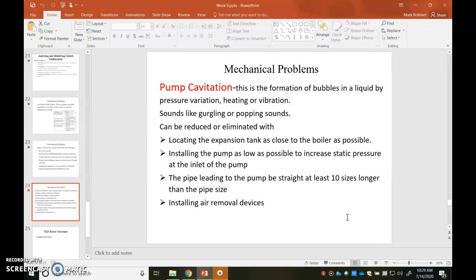boiler and the pump. The pipe leading to the pump must be straight, or at least 10 sizes longer than the pump size. So you can't have an elbow and then the pump. If the pipe is 1 inch, you'll want it 10 inches from that elbow. So without drawing you a picture here, which is making it difficult, you'll just want to make sure the pipe leading to the pump must be straight, or at least 10 sizes longer than the pipe's size. So if it's 2-inch pipe, you want 20 inches of straight pipe in front of it.